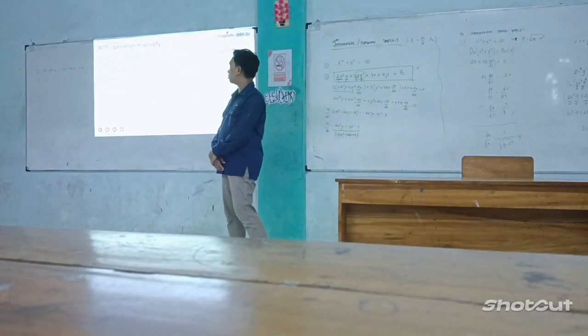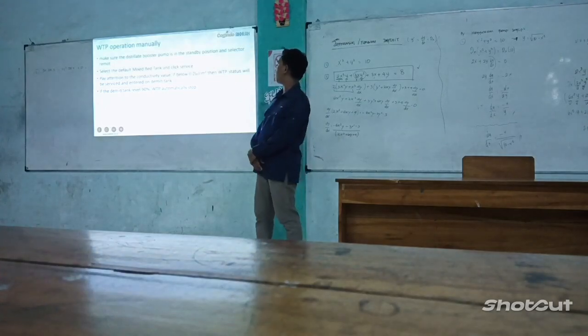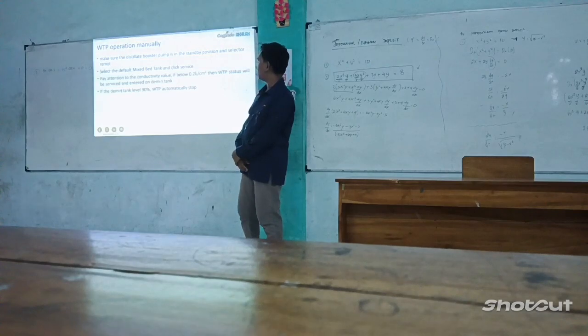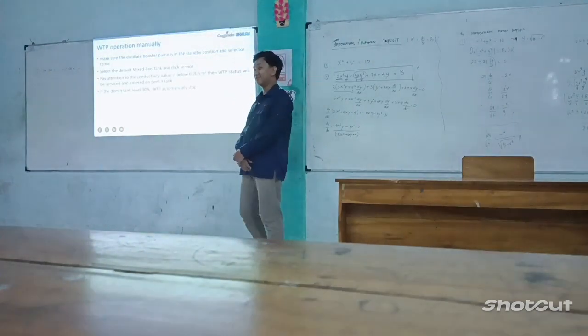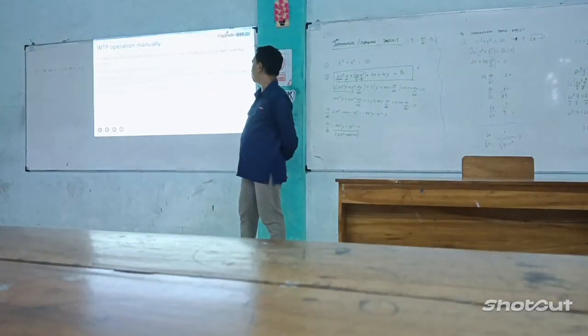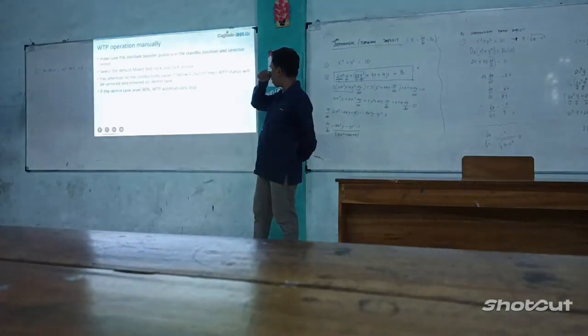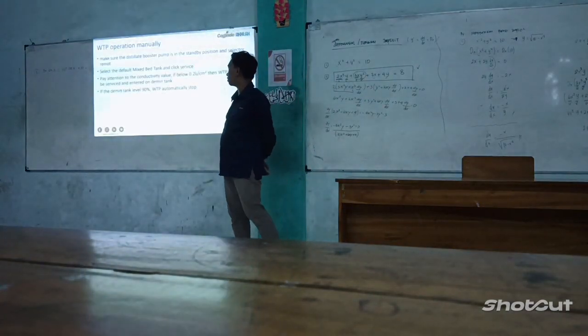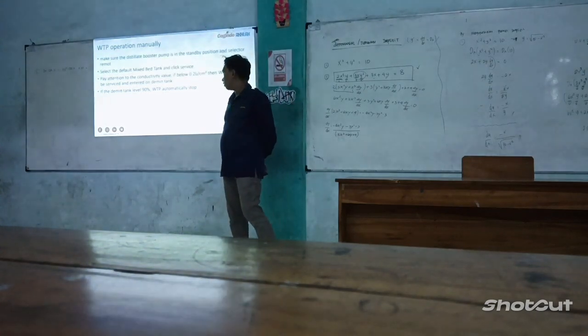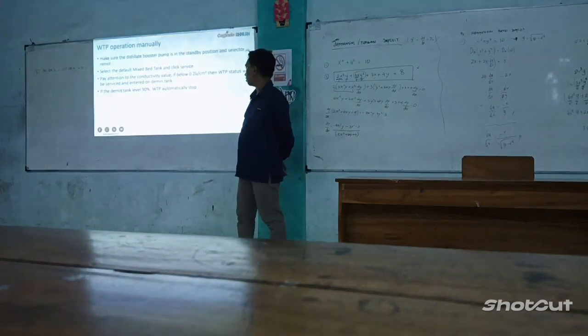Water treatment plant operation manually. Make sure the distillate booster pump is in the standby condition and the selector is on remote. Select the default tank and click service. Pay attention to the conductivity value. If it is below 0.2 microsiemens per centimeter, then the water treatment plant status will be in service and fill the tank. If the demin tank level reaches 90%, the water treatment plant automatically stops.